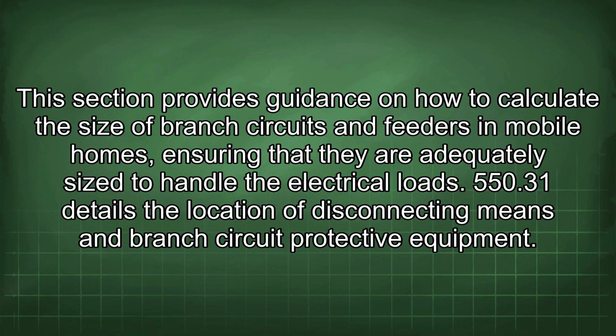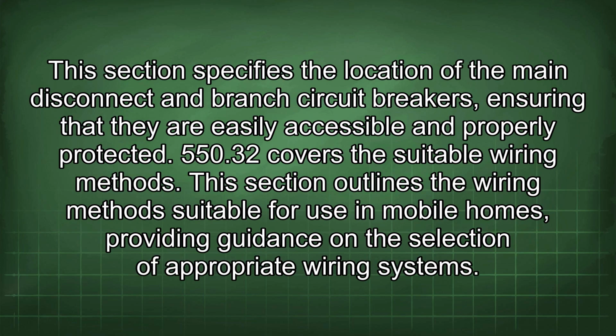550.31 details the location of disconnecting means and branch circuit protective equipment. This section specifies the location of the main disconnect and branch circuit breakers, ensuring that they are easily accessible and properly protected. 550.32 covers the suitable wiring methods. This section outlines the wiring methods suitable for use in mobile homes, providing guidance on the selection of appropriate wiring systems.